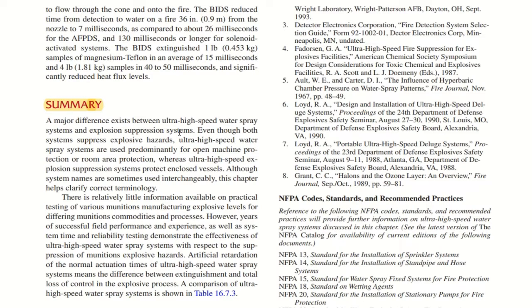There is relatively little information available on practical testing of various munitions manufacturing explosive levels for differing munitions commodities and processes. However, years of successful field performance and experience, as well as system time and reliability testing, demonstrate the effectiveness of ultra high speed water spray systems with respect to the suppression of munitions explosive hazards. Artificial retardation of the normal actuation times of ultra high speed water spray systems means the difference between extinguishment and total loss of control in the explosive process.